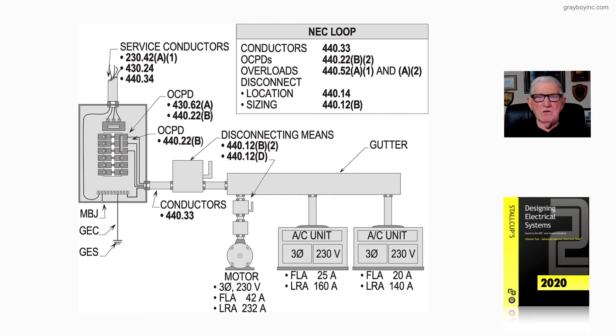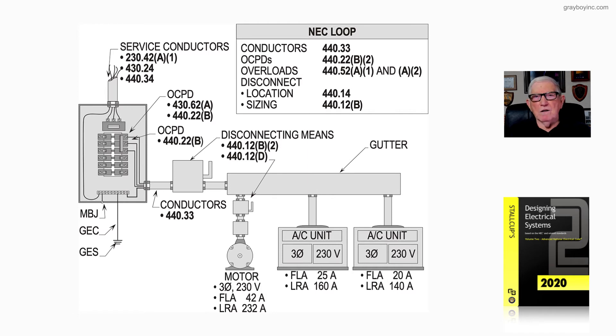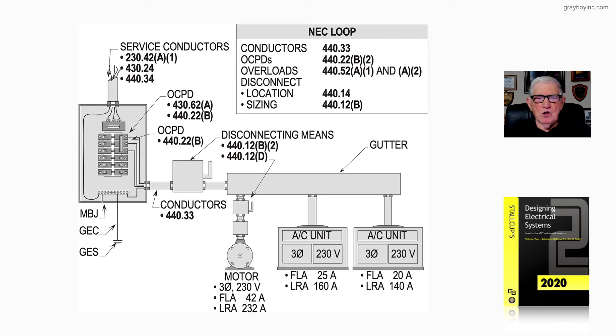The conductors would be sized by 440.33 based upon air-conditioners with motors, or air-conditioners with motors and other loads, or any combination. Now, in the illustration, we show one motor.